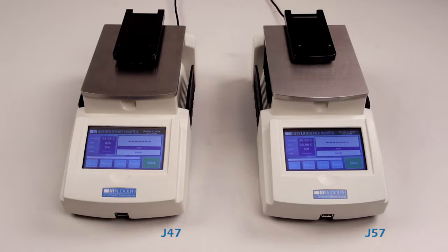What we have here are two nearly identical-looking refractometers, the J47 and the J57. These two instruments have very similar specifications, and they look almost identical. The only way to quickly tell them apart is the J57 has cooling fins, and the J47 does not. What's the difference in actual operation, though? The J47 is temperature-corrected, while a J57 is fully temperature-controlled.